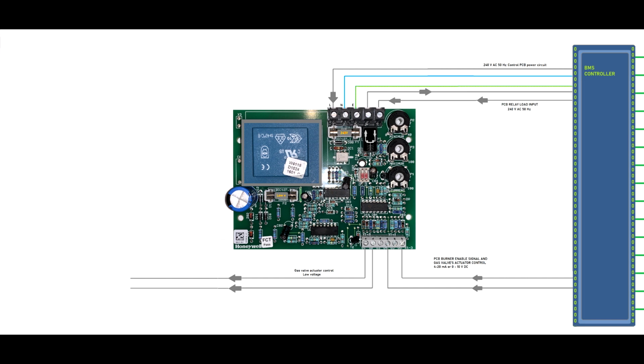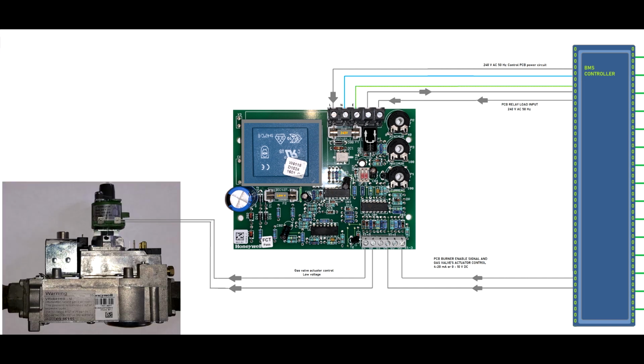Only the top one, which is gray, and the bottom ones, which enables the printed circuit board. Now I use the picture of the real valve and I show you where the wire goes. On the top you have an actuator, and this actuator controls the capacity of this gas valve, allowing more or less gas to pass by.